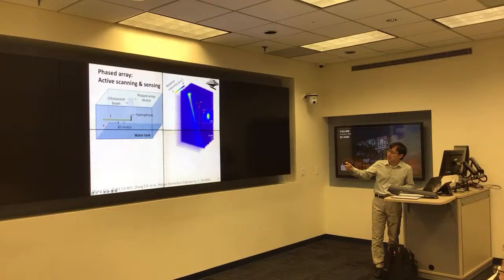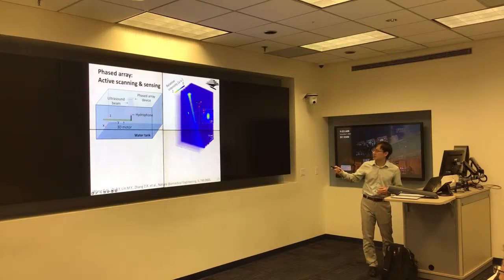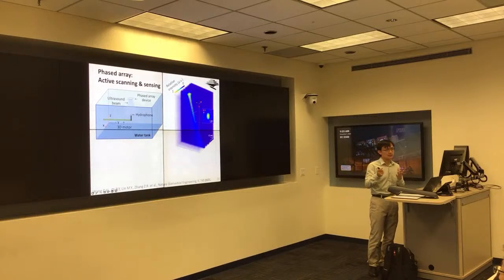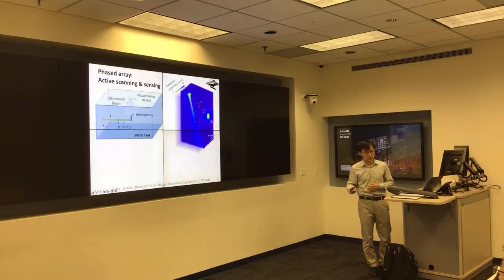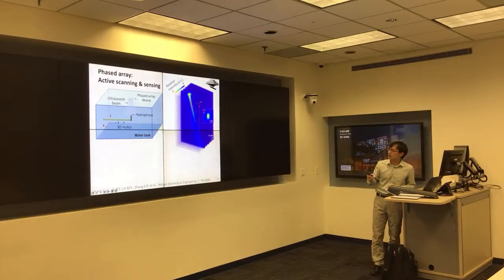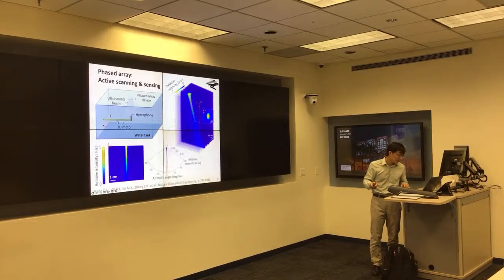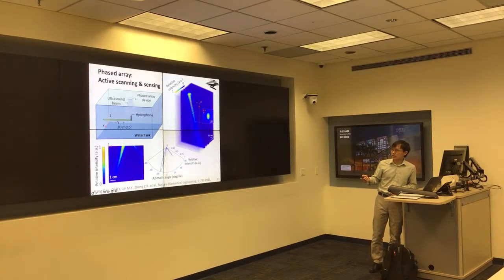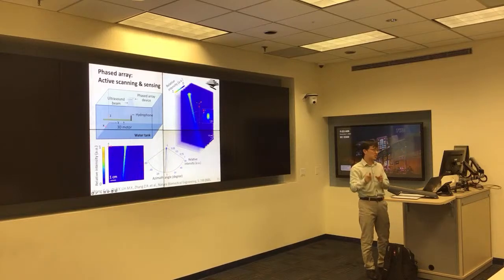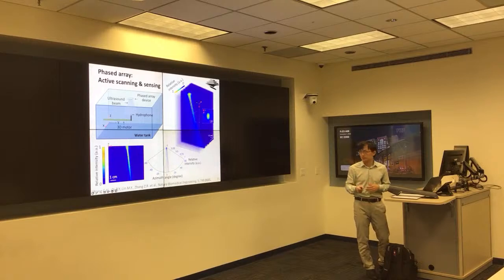This is the patch, and you can focus and steer and emit the ultrasound beam in the water and penetrate as deep as 17 centimeters. The cross section of the ultrasound beam is as small as a few millimeters, and of course this is tunable by the ultrasound frequency, the transducer structure, and also the penetration depth. So this is the GIF image showing that we can do scanning of the ultrasound beam in the water tank and in the human body as well.